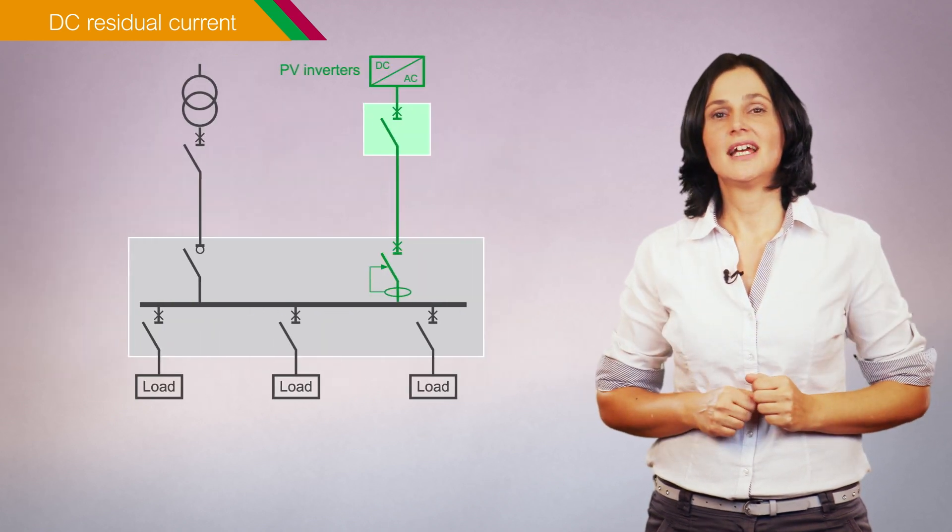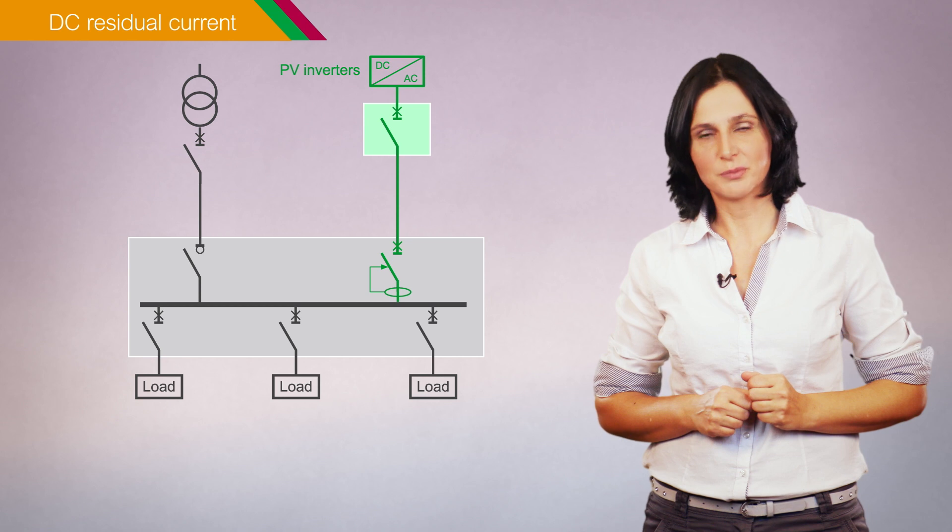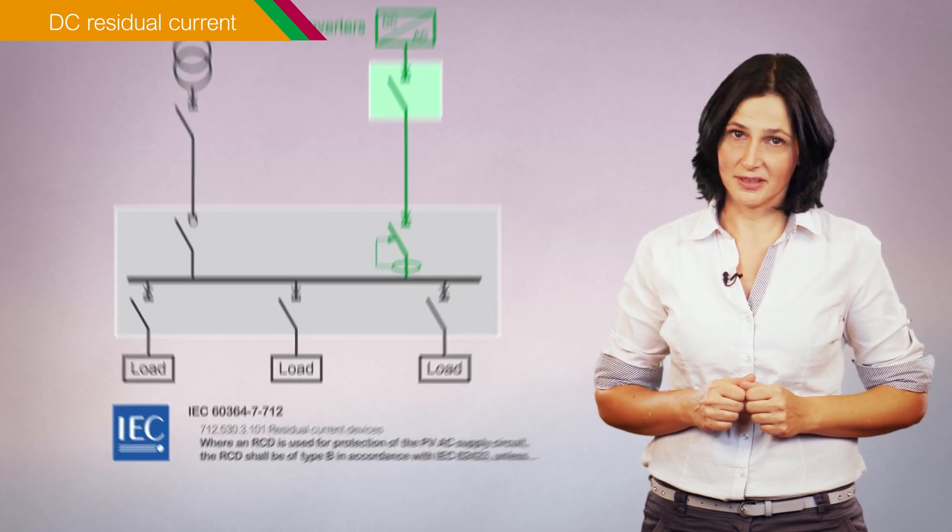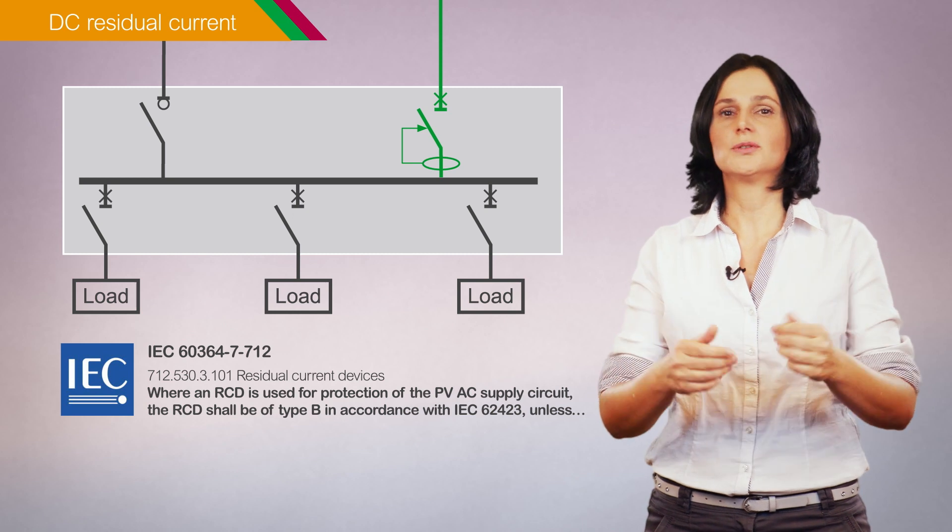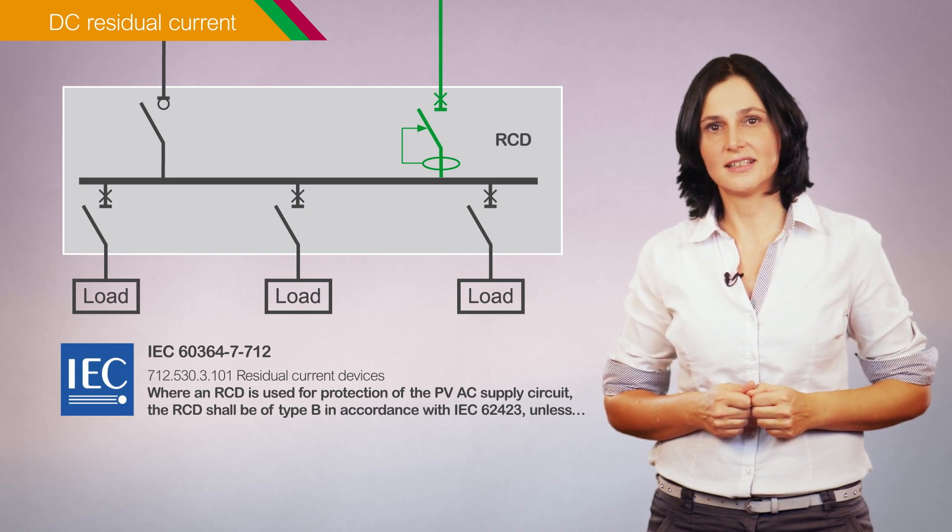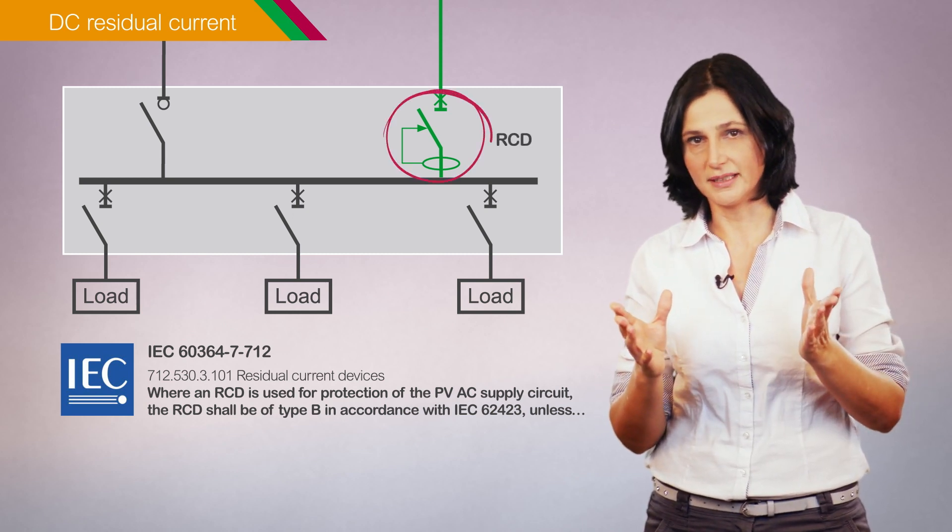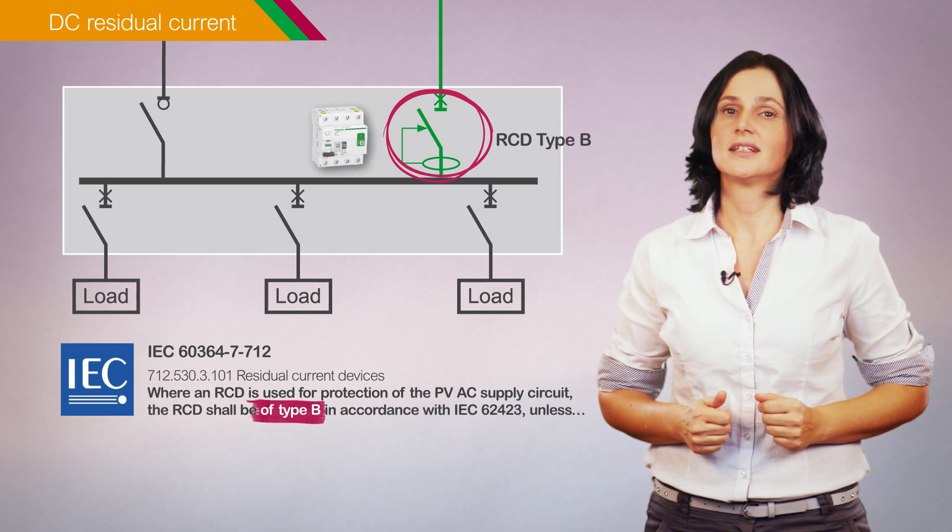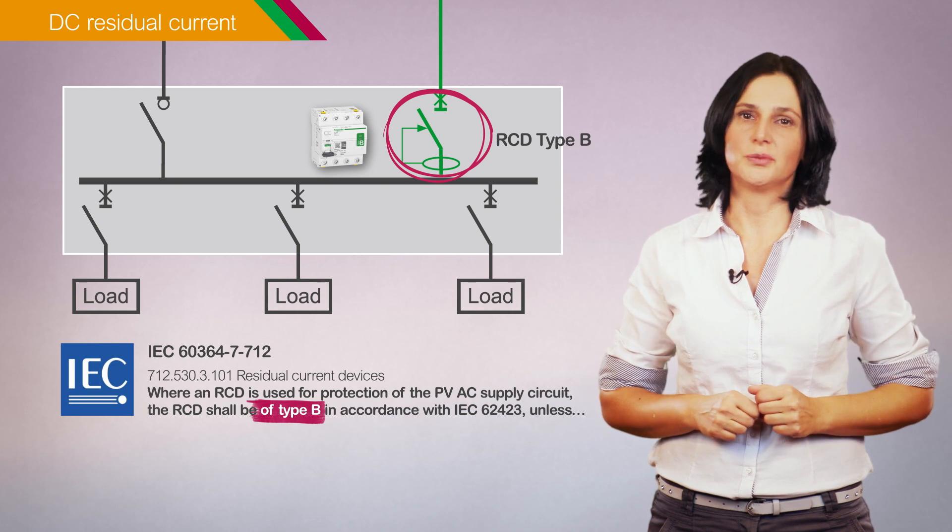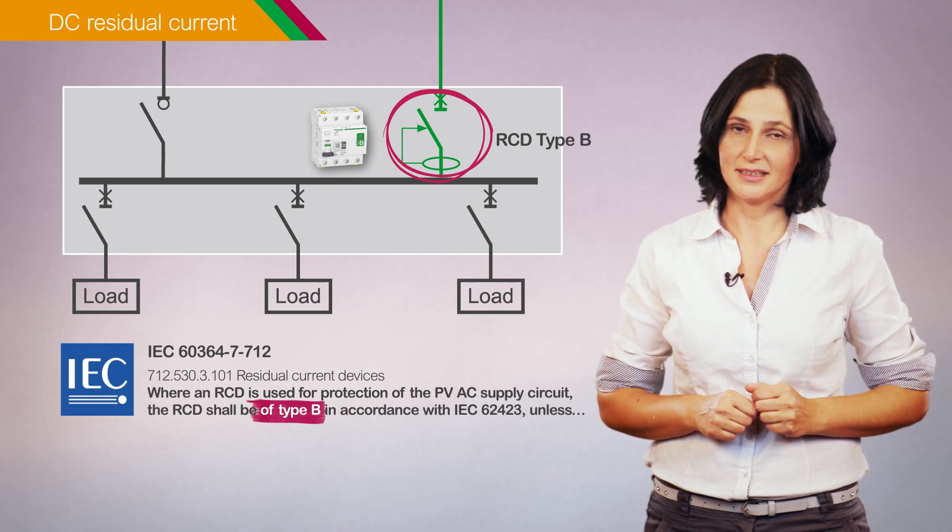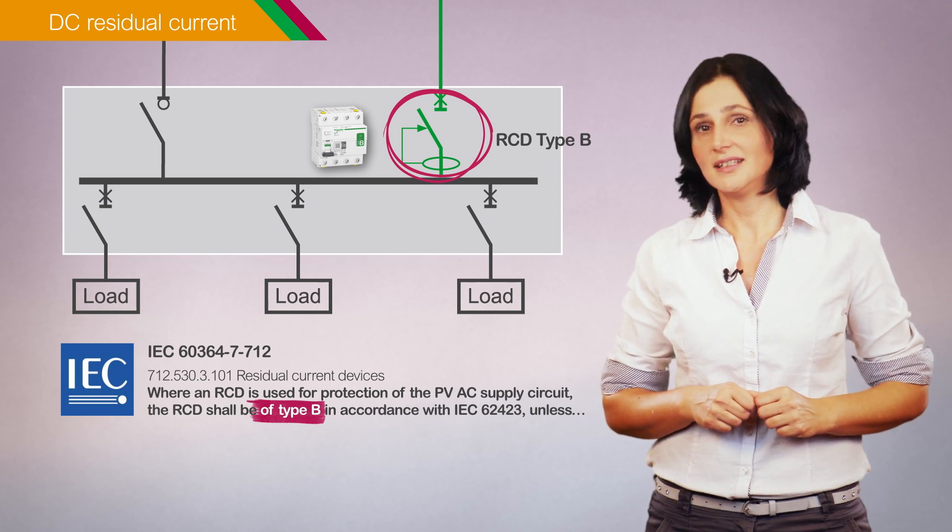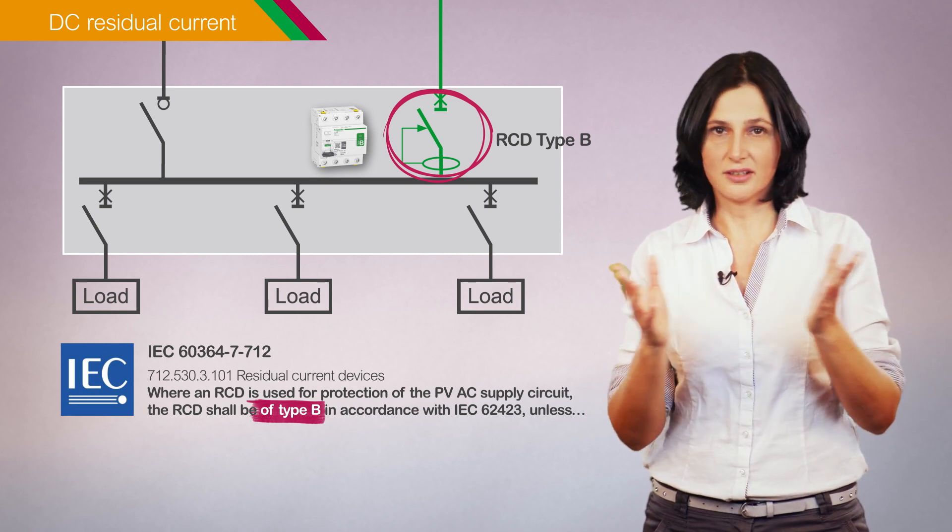DC residual current has an impact on the choice of protection equipment. In particular, as stated by international standards, residual current devices installed on the AC side of the photovoltaic system must be type B, unless there is isolation between AC side and DC side or inverter manufacturer's instructions indicate that type B are not required.